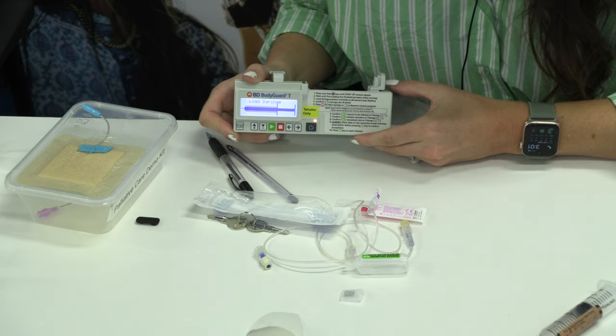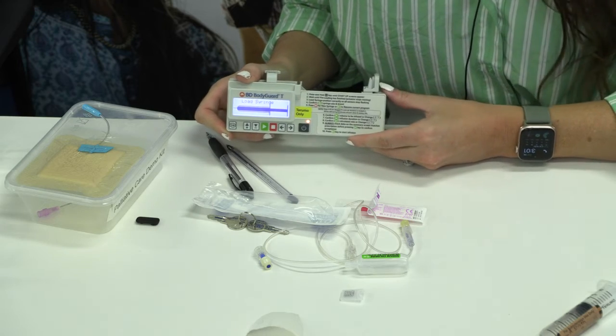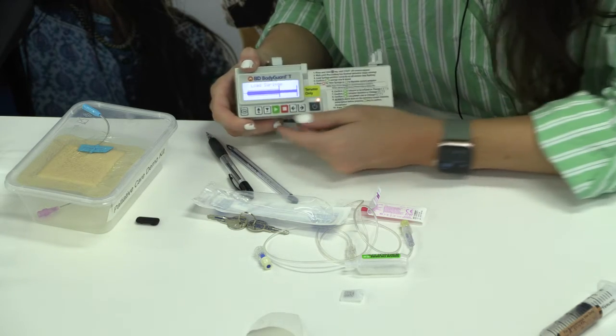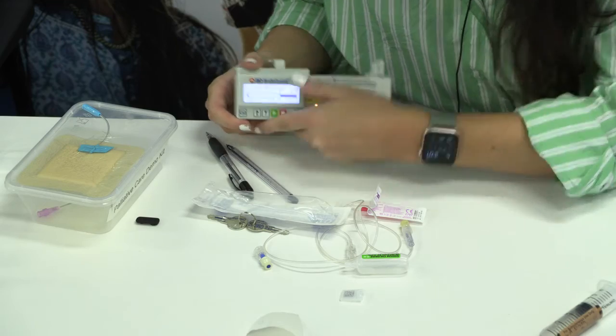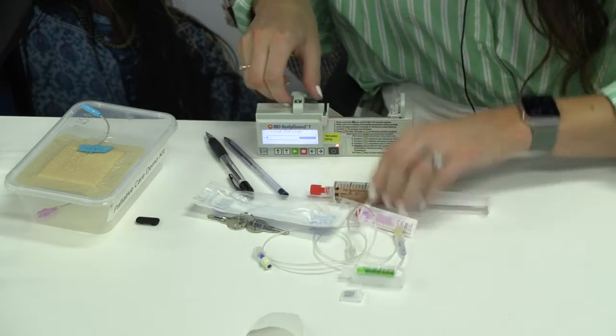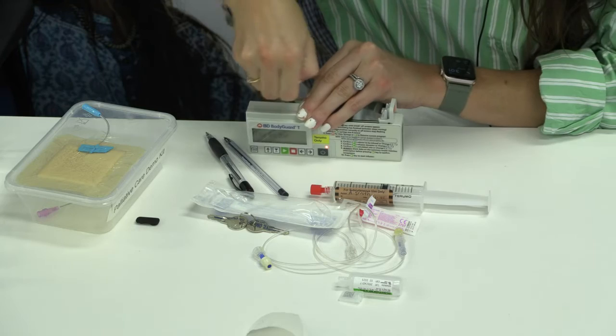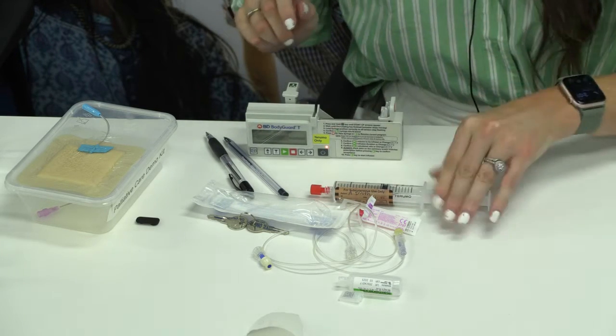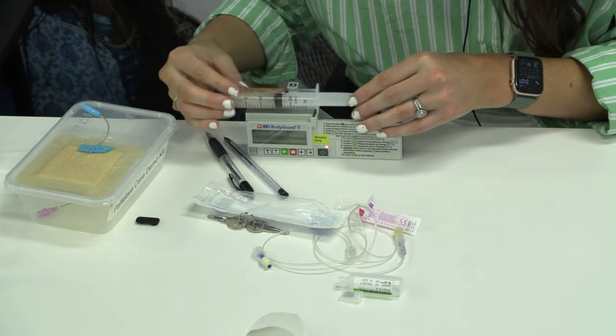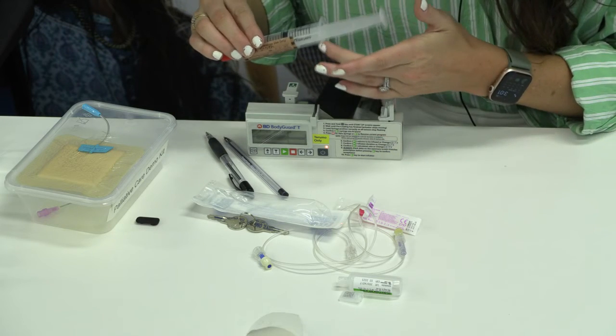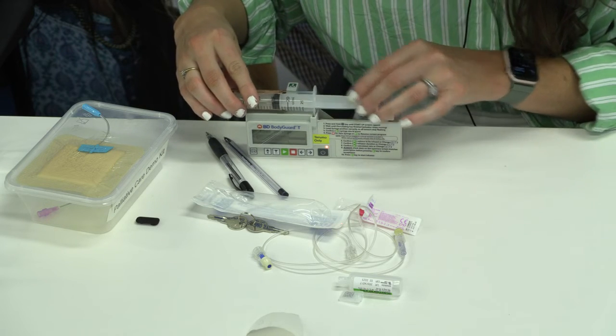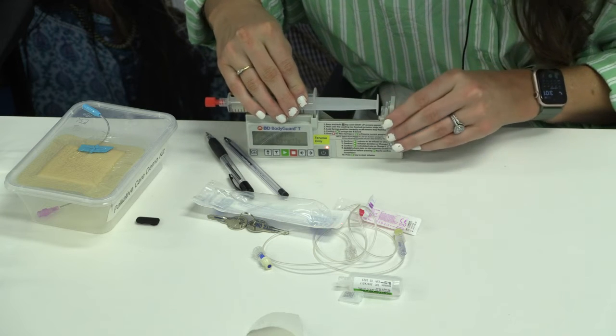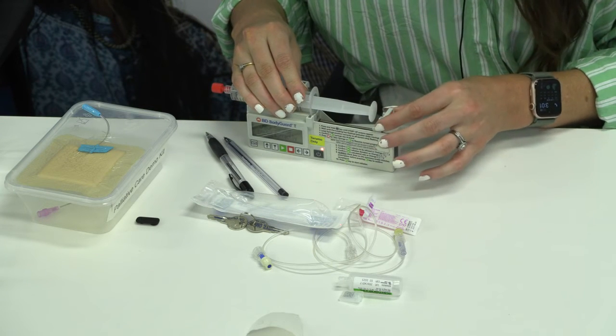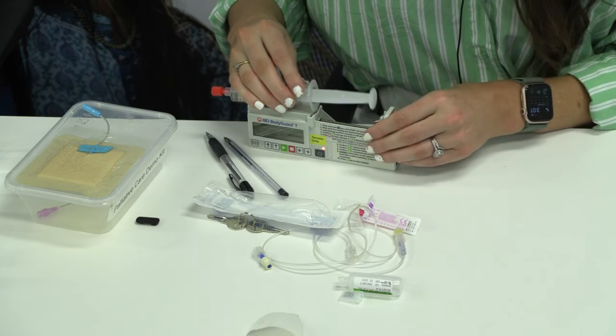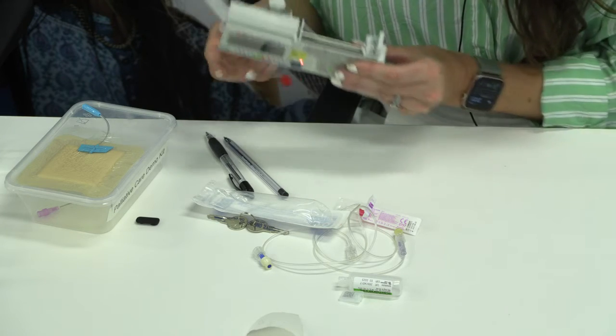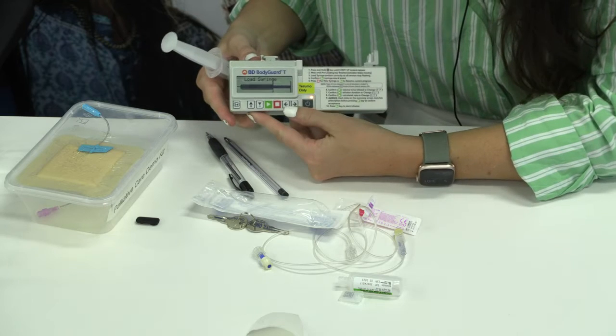If the actuator, in this case the arm, didn't actually move far enough along, you can manually move it back, because we need the arm to sit the syringe within the pump. As you can see, the syringe groove sits within this little divot here, and the actuator doesn't meet that, so you can manually move it, because sometimes the machines won't move the full way.